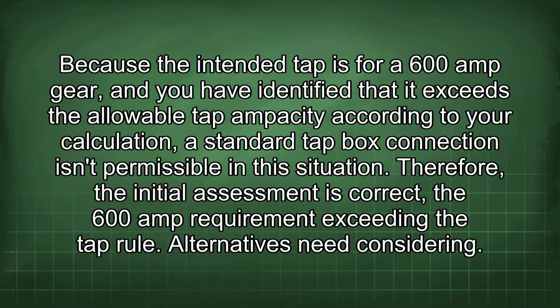Because the intended tap is for a 600 amp gear, and you have identified that it exceeds the allowable tap ampacity according to your calculation, a standard tap box connection isn't permissible in this situation. Therefore, the initial assessment is correct: the 600 amp requirement exceeds the tap rule.